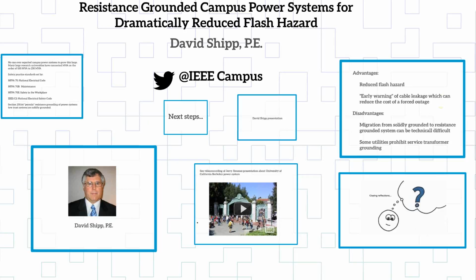I've done a lot of the new equipment design, but as a service industry, 80% of what I did is go into old systems and say, what do I got to do to fix it and modify it and change it so I can get the benefits of the new system? So I've ended up doing a lot of resistance grounded systems. I've converted a lot of high solidly grounded low voltage systems to high resistance. And I've got a lot of tricks up my sleeve on how to do that economically.